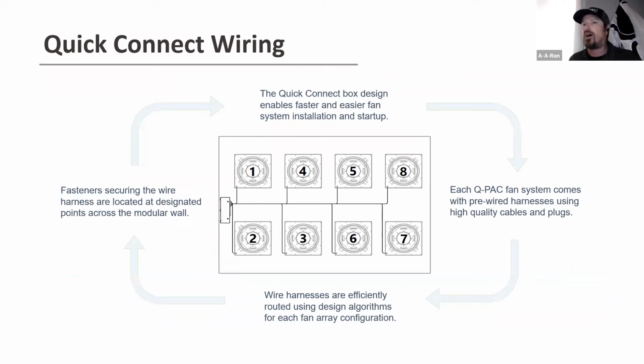When we talk about our quick connect wiring, what makes our system so much easier than other systems is the quick connect box, that small little rectangular box off to the left. And we provide all the wiring harnesses to go to those fans. So you plug in fan 1, there's just a wiring harness with Molex plugs, they connect in there. And so when you have to replace the fans later, all you're doing is disconnecting the wiring harness from the back of the motor, and then you replace that fan and put the new one back on. It takes about 30 minutes or so to replace a fan. So your shutdown for your customer is not very long versus having to pull out a whole system with gantry systems to get a big, large, heavy motor out of it. This also houses all fuse disconnects for the fans, as well as the pressure device for the premium control systems for measuring differential pressure.